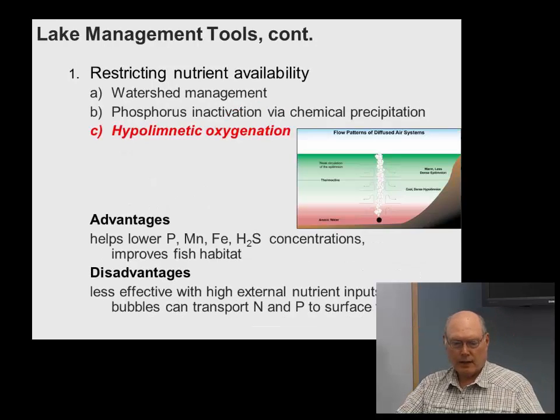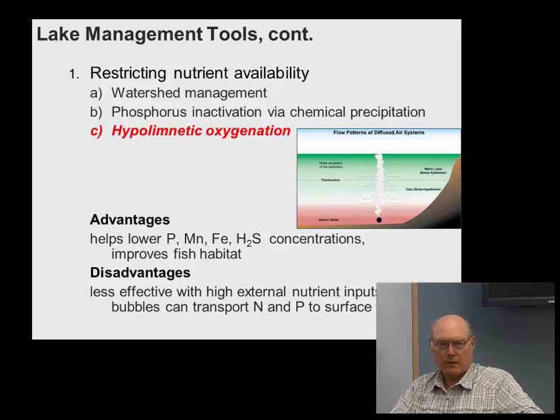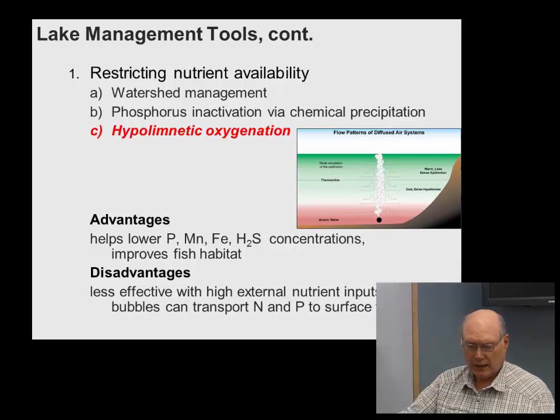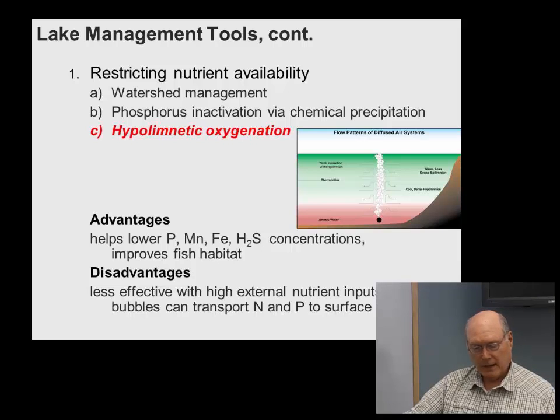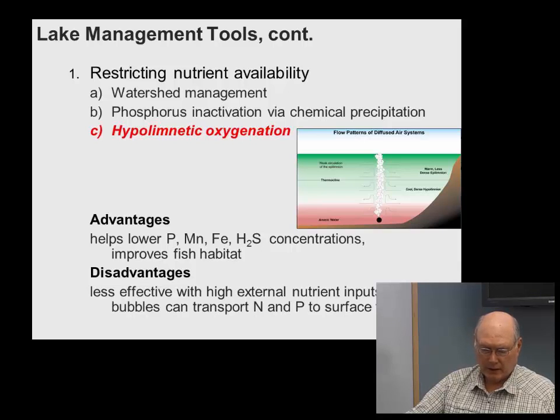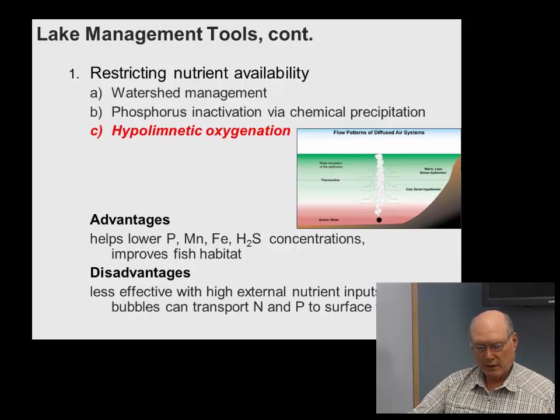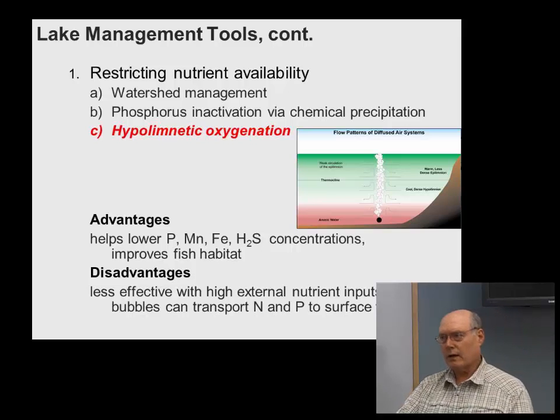A third approach is hypolimnetic oxygenation — oxygenating the bottom sediments. This helps lower phosphorus and other metals like manganese and iron, and improves fish habitat. The disadvantage is that with high external nutrient inputs, rising bubbles can transport nitrogen and phosphorus to the surface water, so while improving overall water quality you can also inadvertently release more nutrients upward.